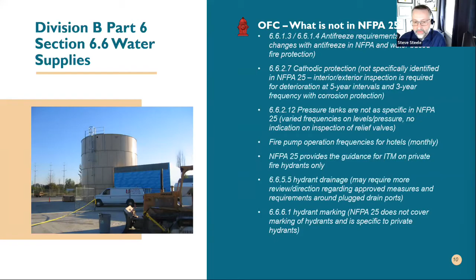But again, hydrants being that of private for NFPA 25, hydrant marking. So that's not necessarily fall into 25 because it's specific to private hydrants, where if you look at NFPA, I believe it's 291, that's for municipal hydrants, the marking of the caps and the head of the hydrant, where private hydrants is kind of a recommendation, if you will. So depending if your municipality is actually enforcing or requiring that to be done, that you won't find in 25 of that language for marking as well.